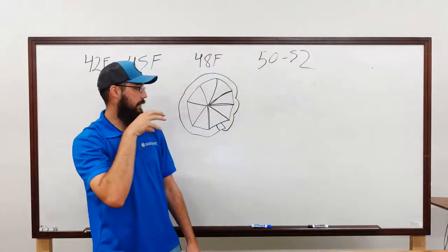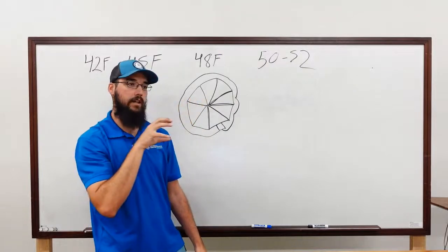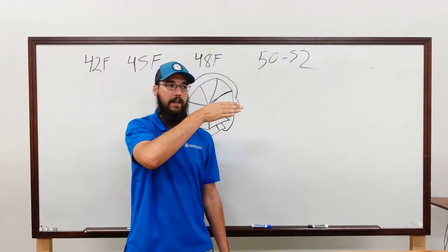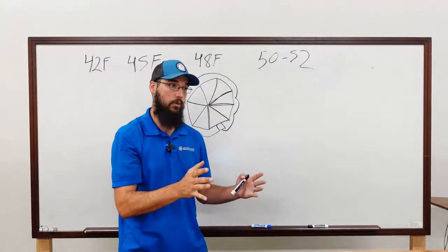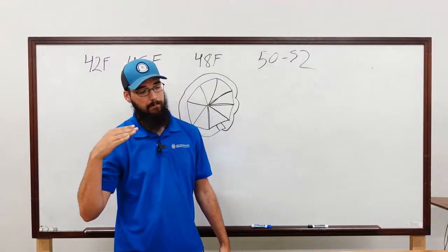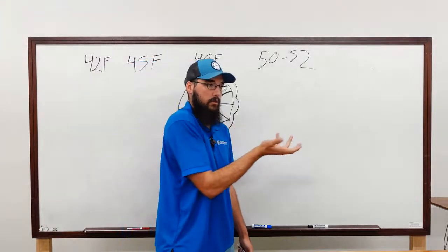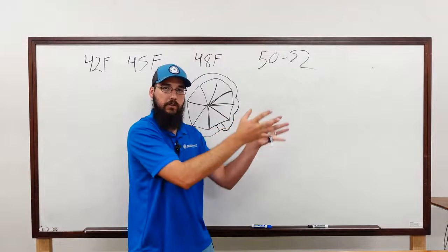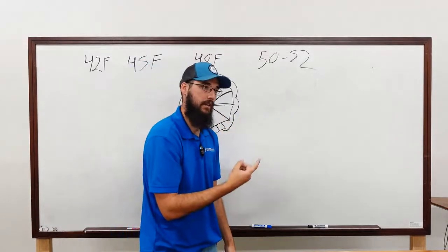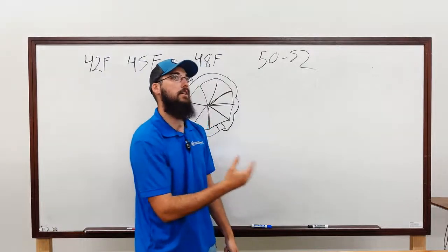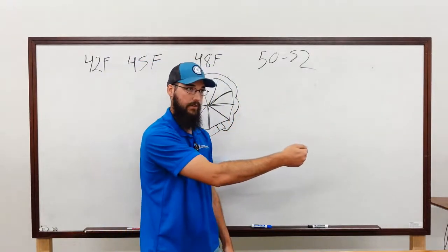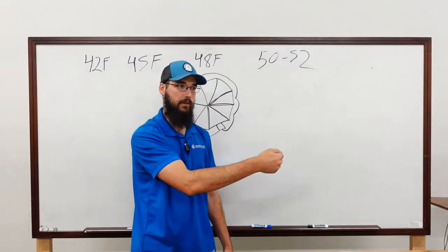Whereas if it comes into the rotation vanes first, and those are typically at some kind of pitch depending on the load, and I'll get to that part in a second, it's able to get a literal pre-rotation. It's able to start to twist that refrigerant in the same direction that the impeller is spinning, so that the impeller has to apply less load to it, or less force. There we go. That's the word.